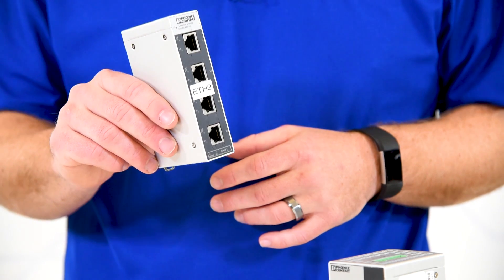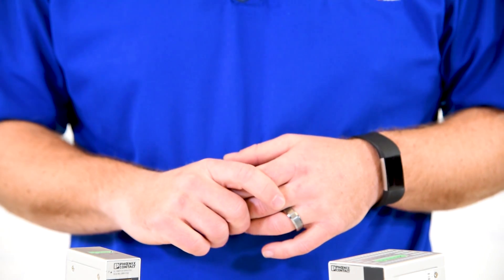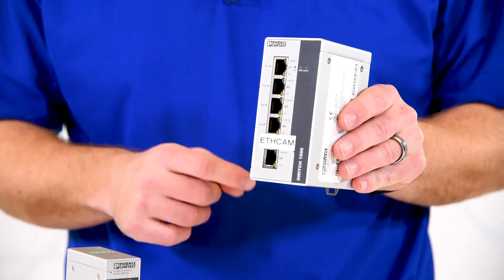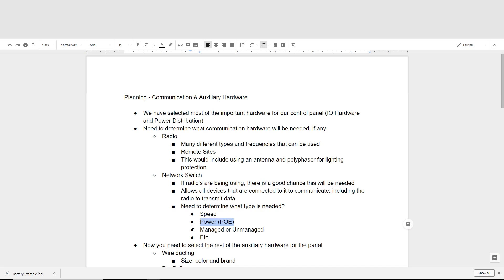When selecting a network switch, there are a few things we need to consider. We need to consider the speed we want the switch to operate at. We also want to consider if we need Power over Ethernet, or PoE, which is commonly used for cameras or other types of devices. We need to determine if it's going to be a managed or unmanaged switch. Managed allows us to control traffic on that network and is a more secure option. There are many other factors to look at when making that selection for your particular control panel.